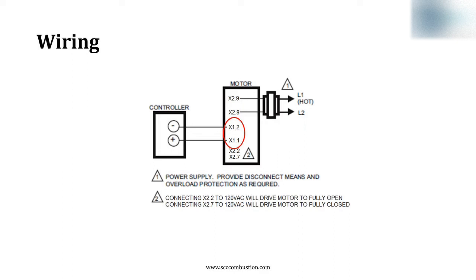To force the actuator fully open, connect 120 volts to X22. And to force it fully closed, connect 120 volts to X27. These terminals can be used for purge and or ignition position commands.